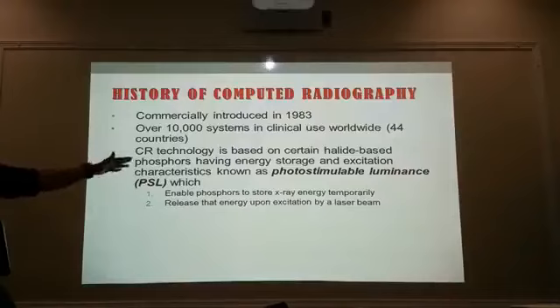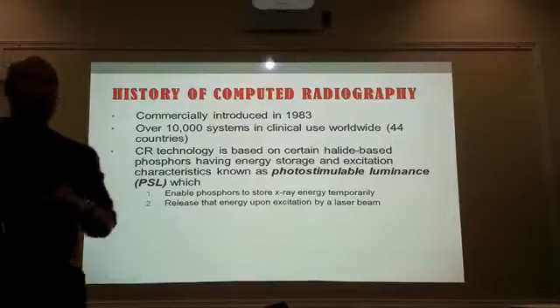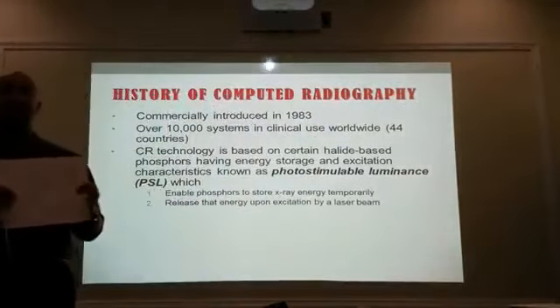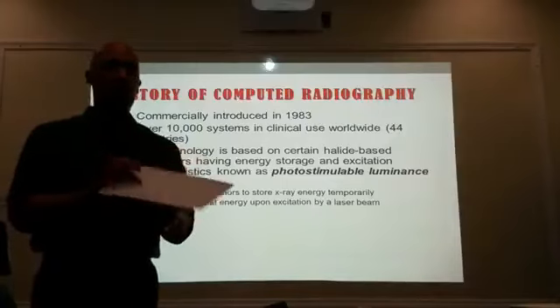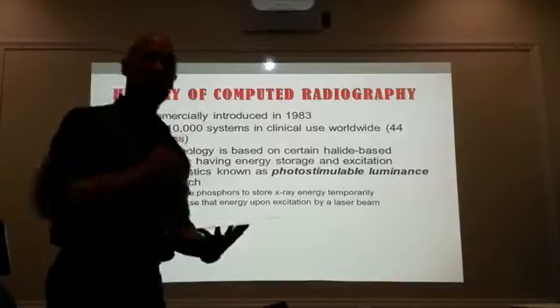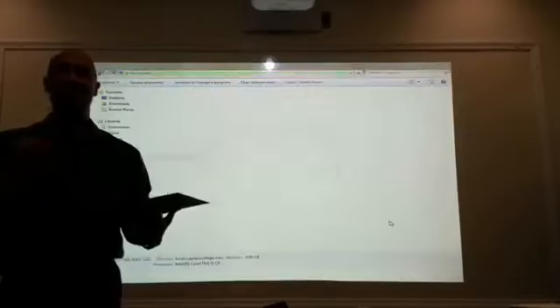These phosphors in the PSP have a characteristic known as PSL, photostimulable luminescence. When the x-rays interact with the screen, the halide-based crystals are going to store that energy until it is scanned at a later time.